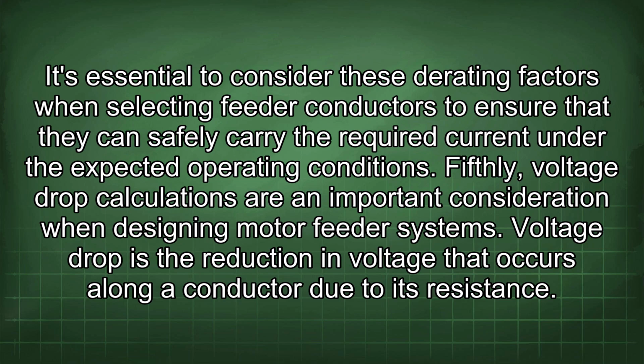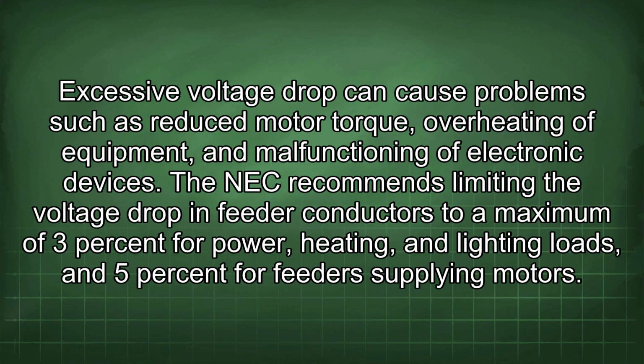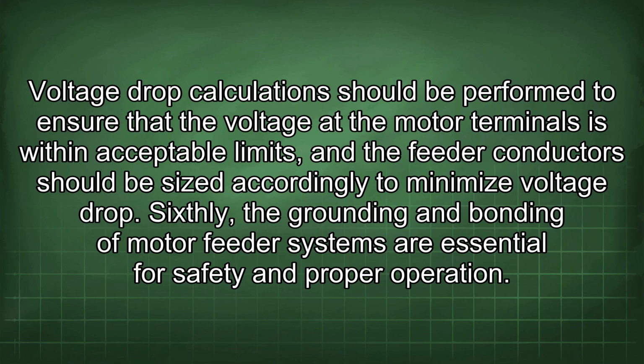Fifthly, voltage drop calculations are an important consideration when designing motor feeder systems. Voltage drop is the reduction in voltage that occurs along a conductor due to its resistance. Excessive voltage drop can cause problems such as reduced motor torque, overheating of equipment, and malfunctioning of electronic devices. The NEC recommends limiting the voltage drop in feeder conductors to a maximum of 3% for power, heating, and lighting loads, and 5% for feeders supplying motors. Voltage drop calculation should be performed to ensure that the voltage at the motor terminals is within acceptable limits, and the feeder conductor should be sized accordingly to minimize voltage drop.